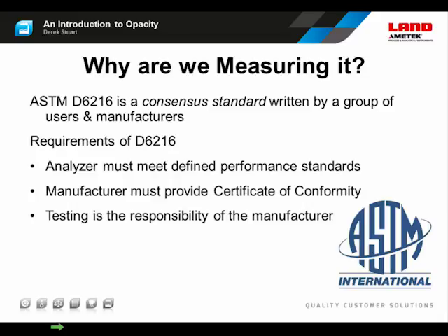Now that's the US regulation. In Europe, compliance emissions monitors do have to be third-party tested. So the 4500 Mark III was tested in Germany by the TÜV organization, and we have a test certificate and a test approval according to EN 15267. So the instrument has been approved in Europe. So we have both the self-certification that's required in the United States, and we have third-party approval in Europe.